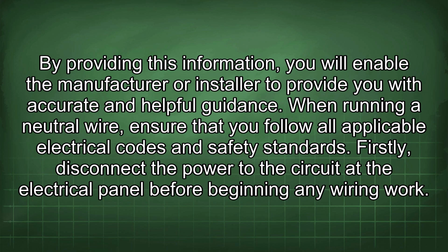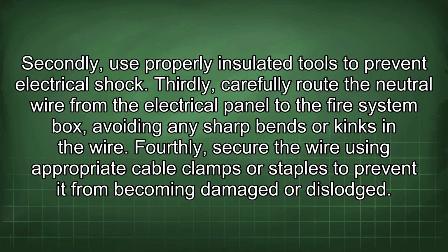When running a neutral wire, ensure that you follow all applicable electrical codes and safety standards. Firstly, disconnect the power to the circuit at the electrical panel before beginning any wiring work. Secondly, use properly insulated tools to prevent electrical shock. Thirdly, carefully route the neutral wire from the electrical panel to the fire system box, avoiding any sharp bends or kinks in the wire. Fourthly, secure the wire using appropriate cable clamps or staples to prevent it from becoming damaged or dislodged.